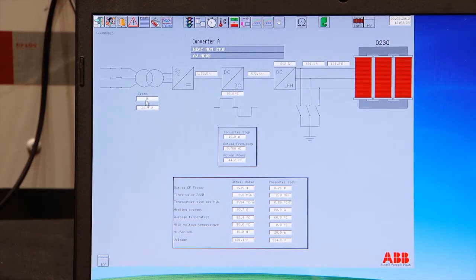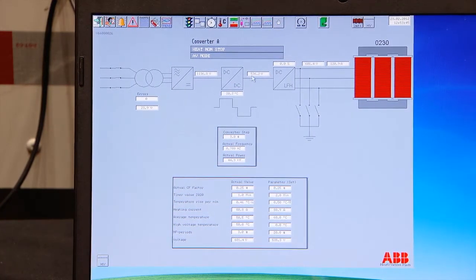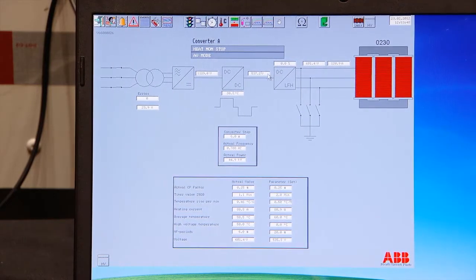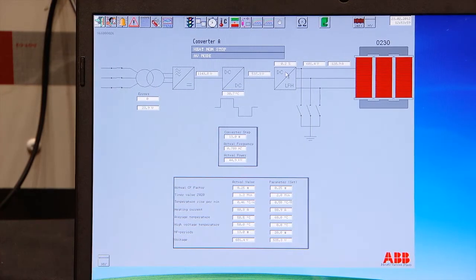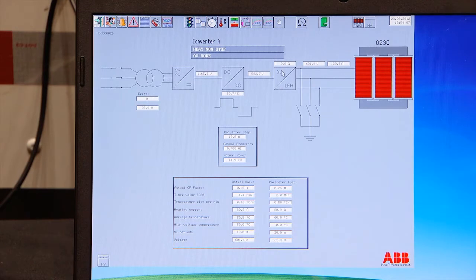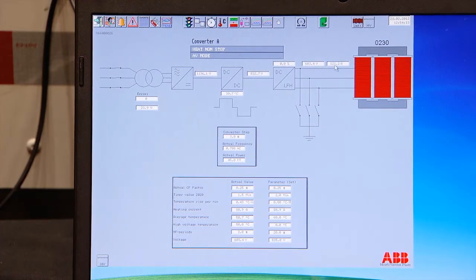And we also have the intermediate voltage. That's the first DC link. That's pure rectified from the net grid voltage. We have the second, that's the output DC link shown. We have the percentage of the chopper working, that's the output chopper, taking care of whatever energy is coming back from the transformer. So if this voltage goes too high on the output DC link, the chopper will burn it in the chopper resistors. And these two last values are the peak values of the voltage and the current.